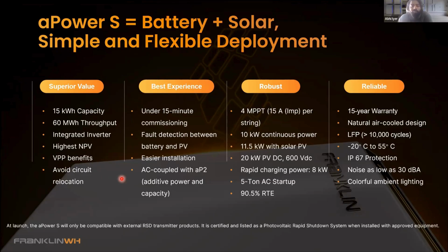We do have 4 MPPTs here. Again, speaking more for the design folks, 4 MPPTs, which is 15 amps per string. If you do have bifacial or larger modules, which have an IMP larger than 15 amps, say 17 amps or 18 amps, we're still going to be limiting it to 15 amps. At that point, you're just going to be focusing on the string voltage calculations.